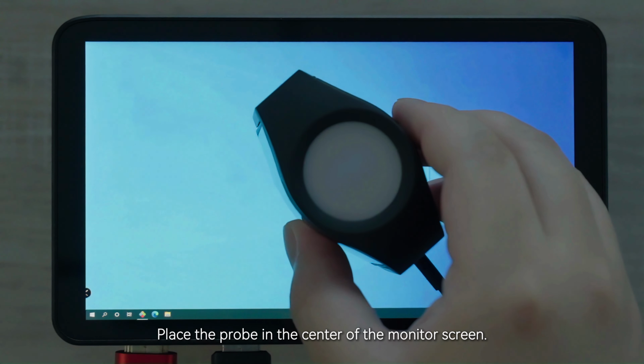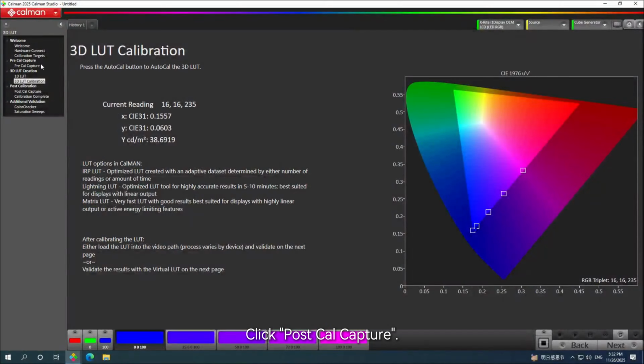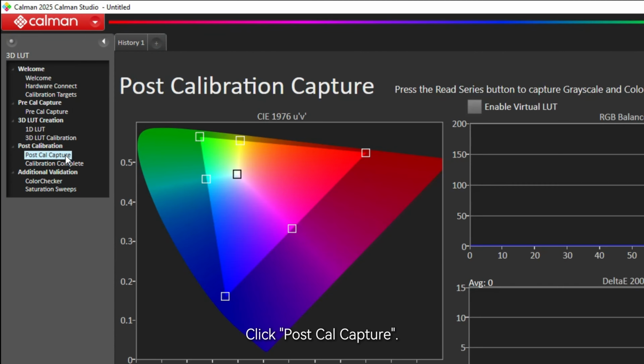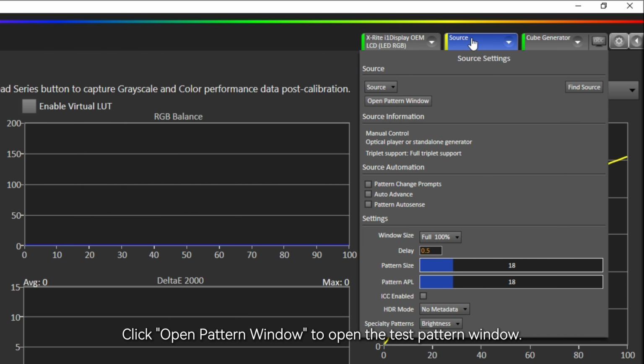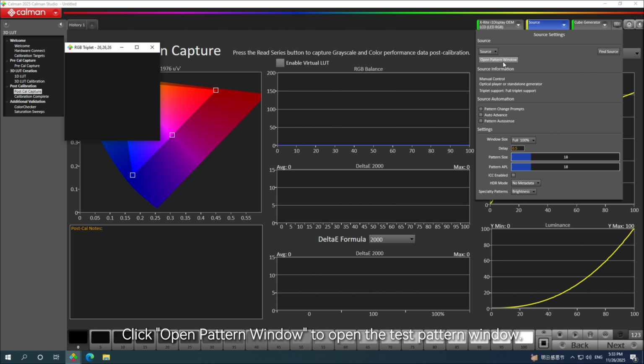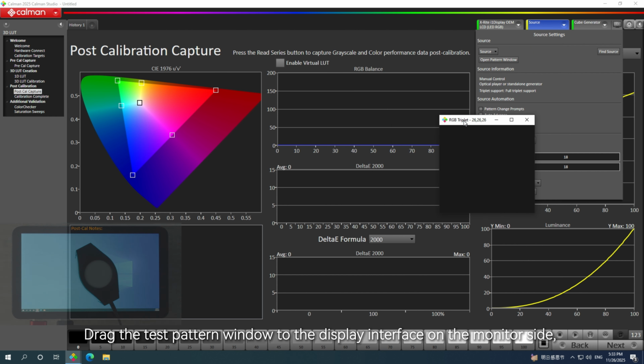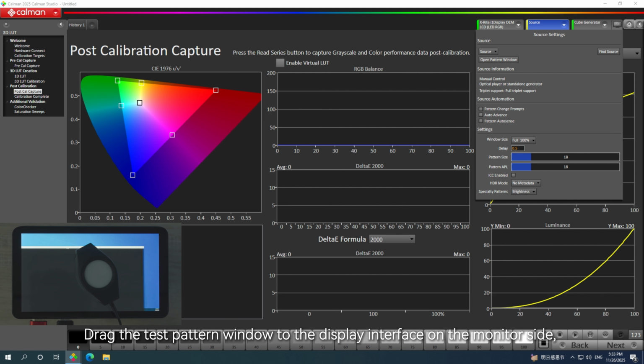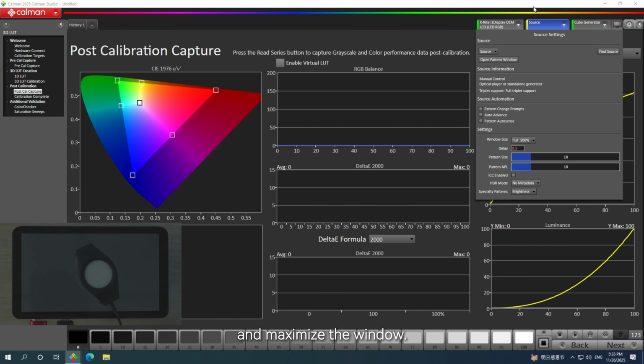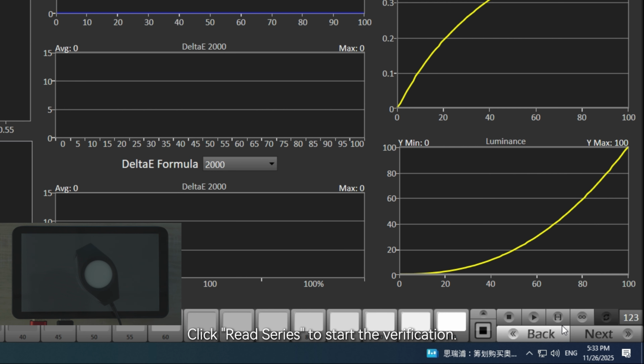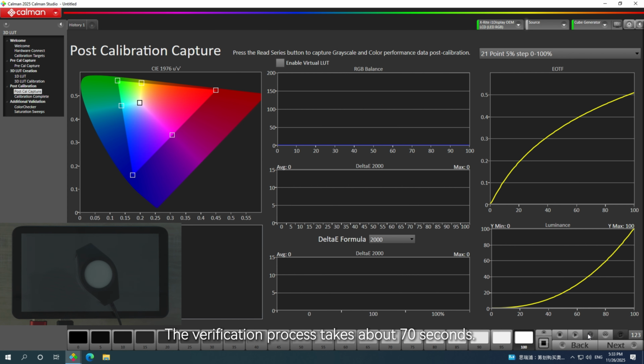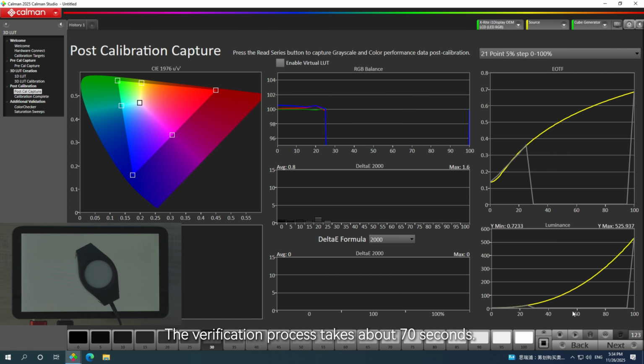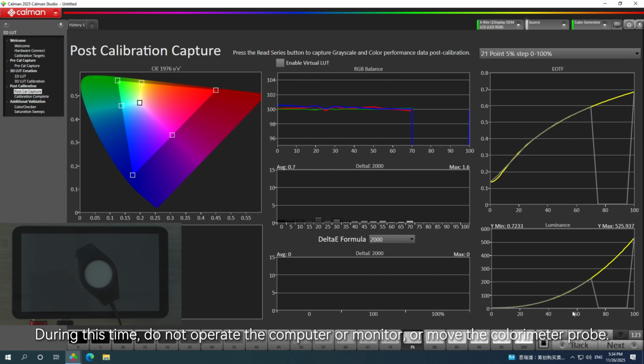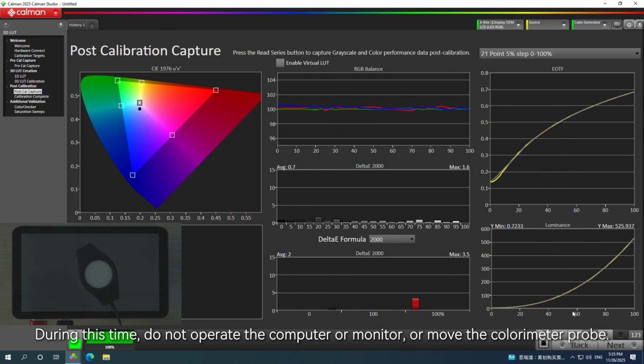Place the probe in the center of the monitor screen. Click Post Cal Capture. Click Source. Click Open Pattern Window to open the test pattern window. Drag the test pattern window to the display interface on the monitor side and maximize the window. Click Read Series to start the verification. The verification process takes about 70 seconds. During this time, do not operate the computer or monitor, or move the colorimeter probe.